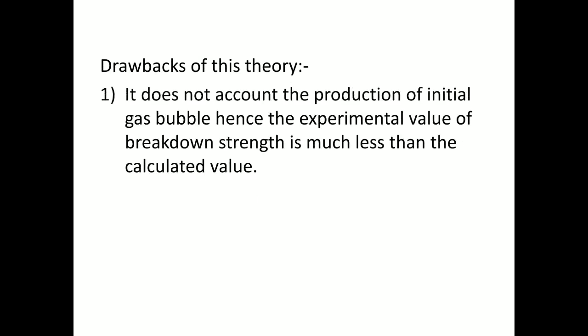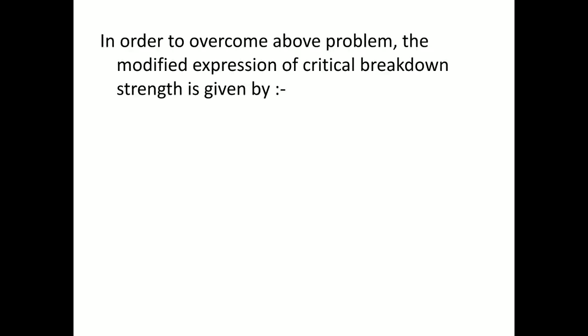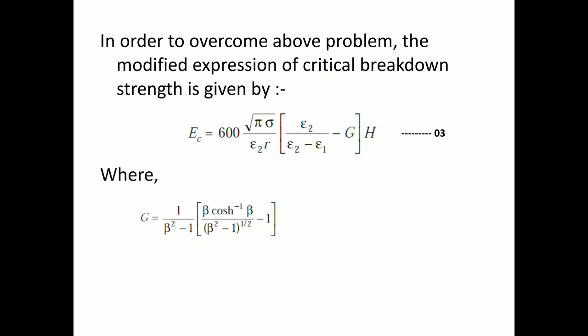Let us discuss the drawbacks of the cavity breakdown mechanism. The first drawback is that this theory does not account for the production of the initial gas bubble, because of which the experimental value of breakdown strength is much less compared to the calculated value. The second drawback is that this mechanism assumes the gas bubble will elongate in length keeping the overall volume constant, but this is practical only for water bubbles by applying the simple gas law PV = RT. To overcome these problems, the modified expression of critical breakdown strength according to cavity breakdown mechanism is given by equation number 3, where capital G and capital H are additional terms defined by their respective expressions.